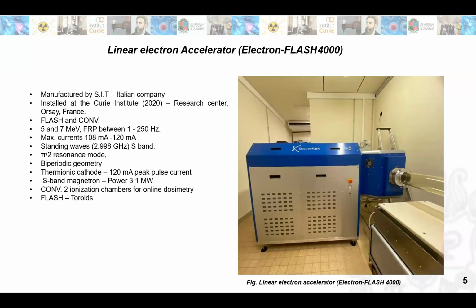In conventional mode, the LINAC uses two inline ionization chambers for dosimetry. However, in flash mode, these chambers are automatically retracted to avoid saturation, and two beam current transformers, toroids, are inserted to monitor the beam current and pulse duration in real time.